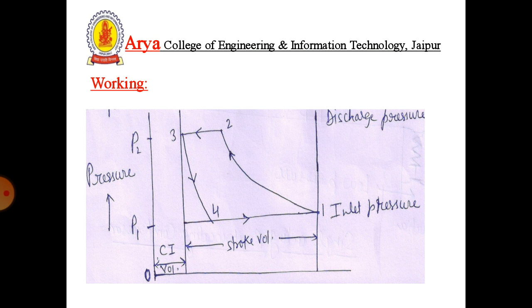When the piston reaches point 2 on the indicator diagram, the exhaust valve starts to open and the suction valve remains closed. The discharge portion of the cycle is shown at point C on the indicator diagram. The gas is discharged at the discharge line pressure P2 when the piston reaches point 3. It has traveled to the upper end of the stroke. Physically, at this point in the stroke, there is a space between the piston face and the head. This space results in a trapped volume and is called clearance volume.